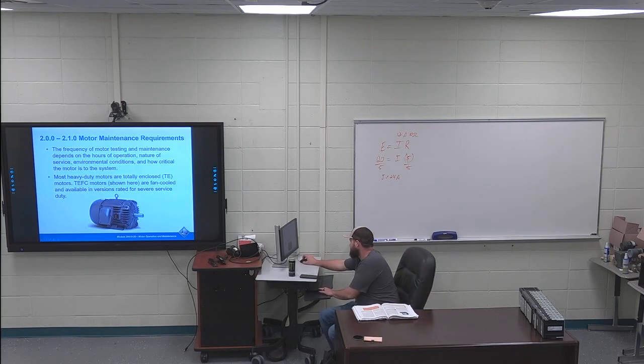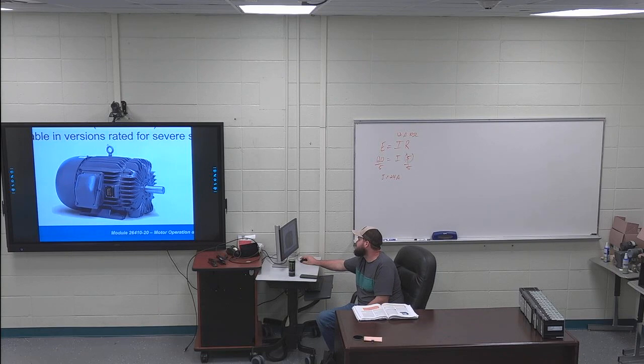So you can see this motor that's on the board. If I zoom in, you can see this eye bolt that screws in the top. Most if not all motors have a part where you can screw in an eye bolt and then pick them up and move them around. You're never picking them up by the ends. You're going to damage the bearing picking them up there.